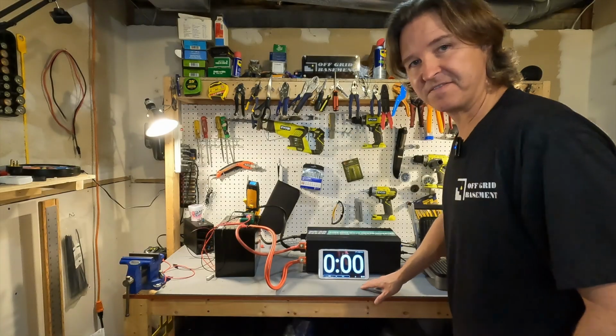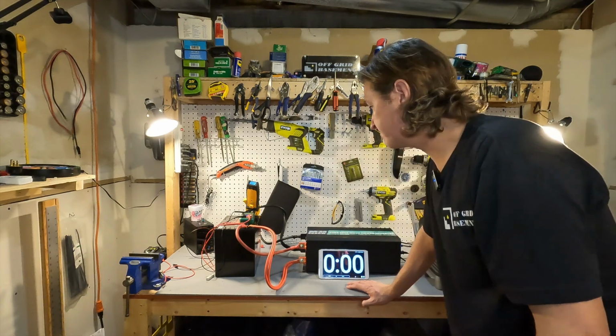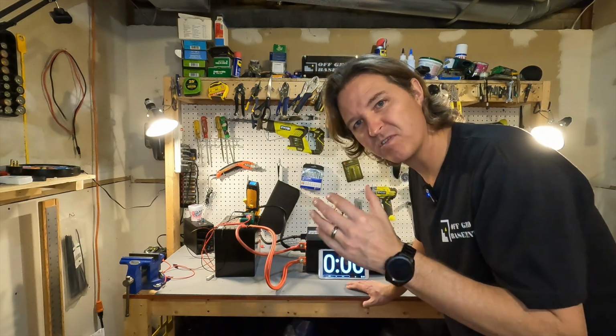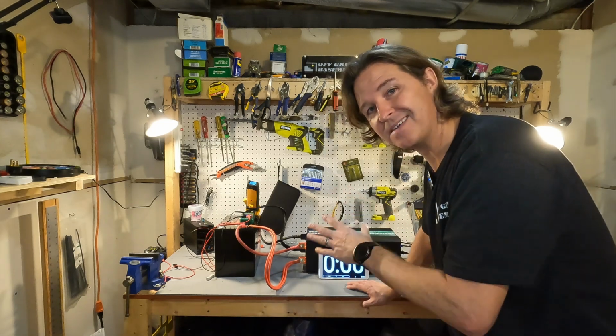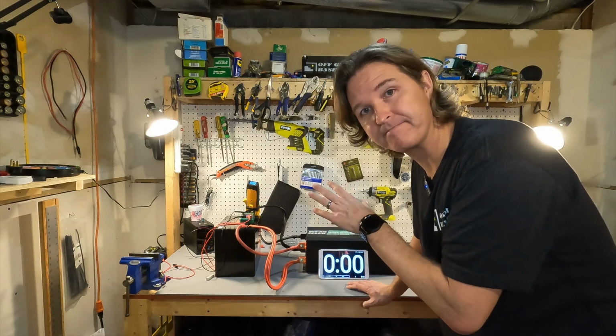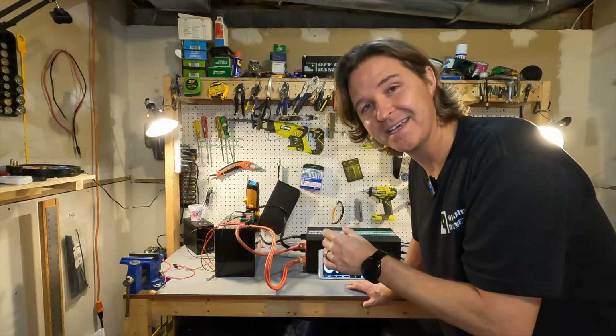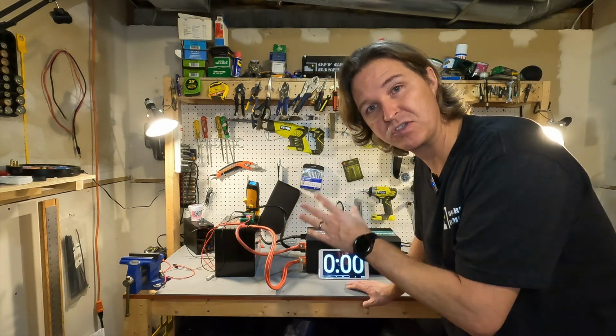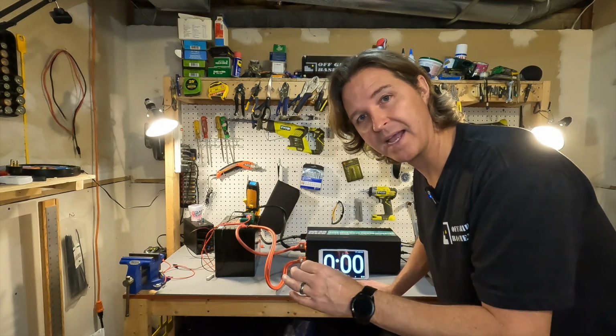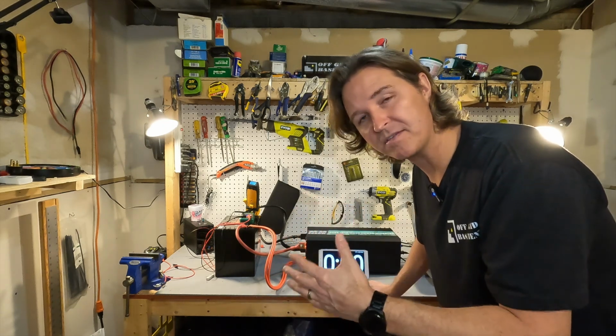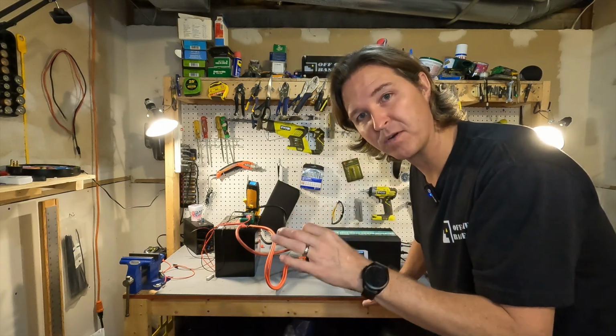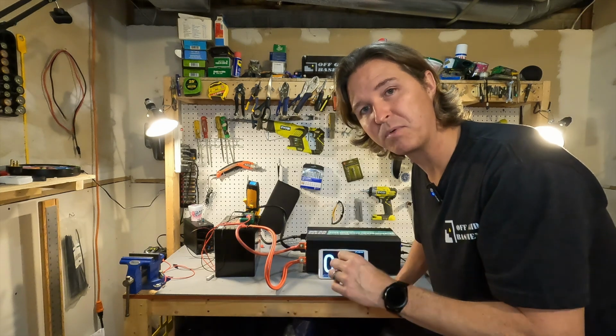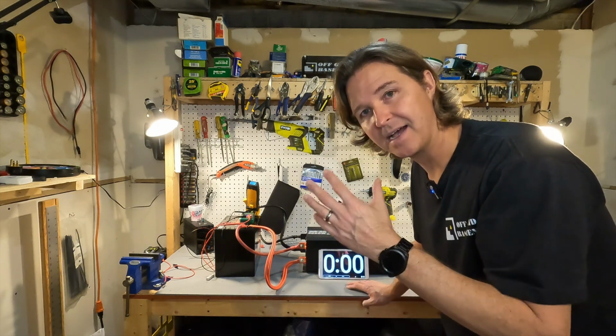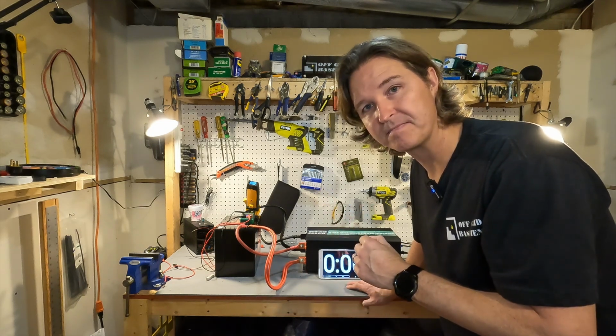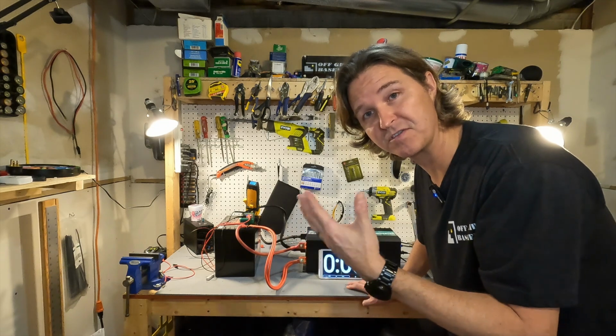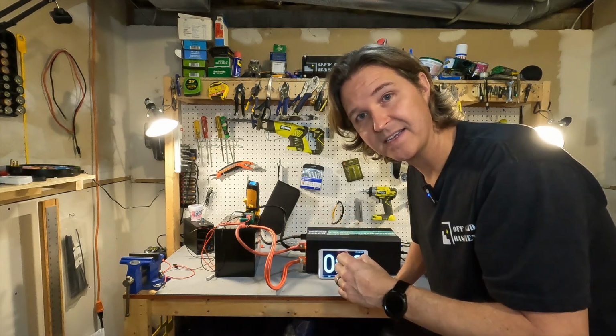I've given this battery about 5 minutes to cool down, and so we're gonna go ahead and do roughly a 200 amp test. Now, honestly, this battery should shut down after a minute, I'm gonna give it a minute. It should shut down after like 10 or 15 seconds of having 200 amps, because it really shouldn't pull 200 amps for an extended amount of time. It can pull 100 amps for an extended amount of time, because that's what it's rated for at its maximum. But 200 amps, it really shouldn't pull for more than 10 to 15 seconds. I'm gonna give it a minute or two, because I don't want to burn this battery up. The internals could actually start getting dangerously hot at these amps.